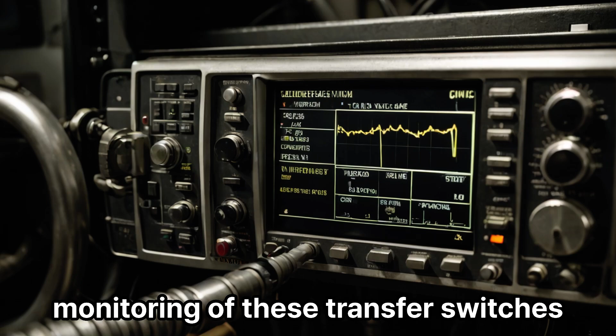Moving forward, predictive intelligence and battery health represent the next, essential frontier in emergency power optimization. We must evolve beyond the outdated practice of scheduled voltage tests, which offer only a fleeting snapshot in time and can miss critical degradation between test cycles. Instead, we need to implement 24/7 real-time internal impedance monitoring for every single cell within our extensive battery banks. This granular level of data collection provides truly invaluable insights into the precise health and performance of each individual cell. With this wealth of information, sophisticated, AI-driven analytics can then be deployed effectively to predict chemical degradation and the potential for thermal runaway long before any actual failure occurs.